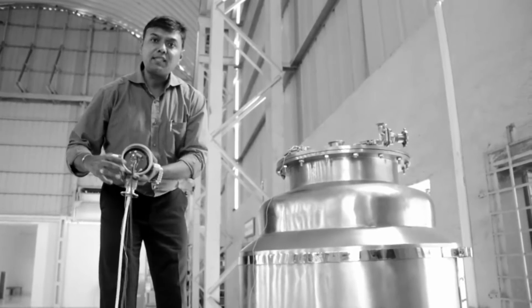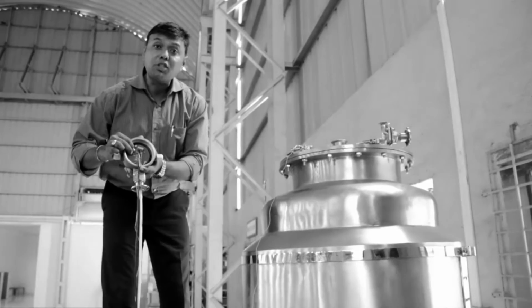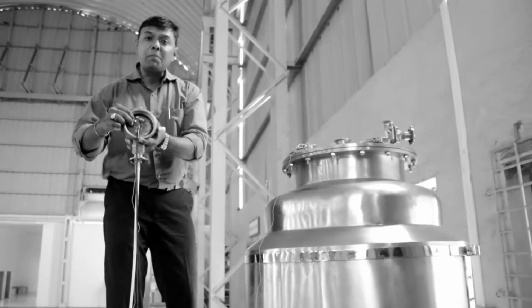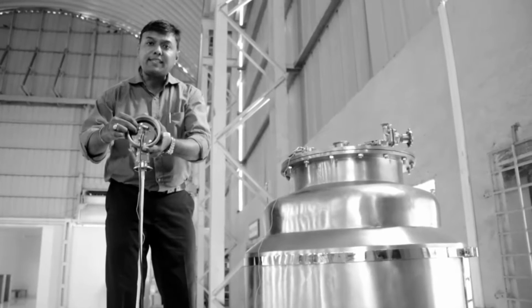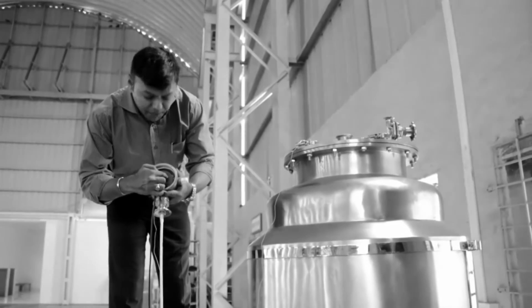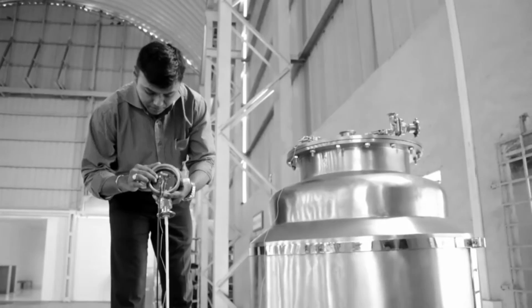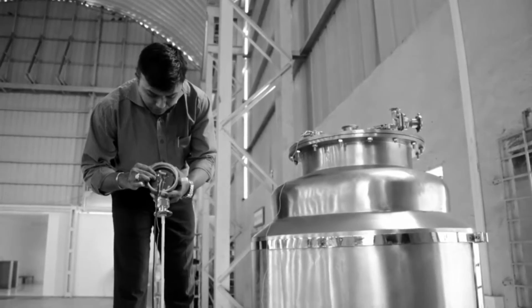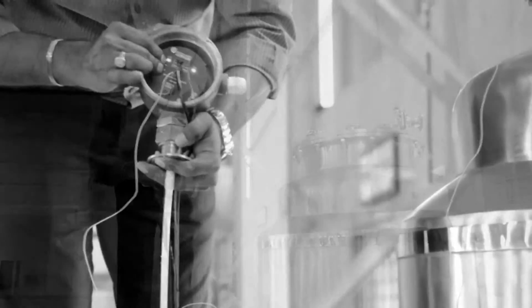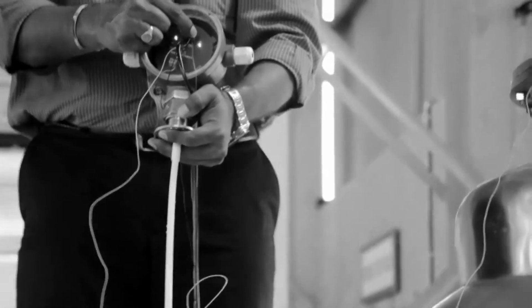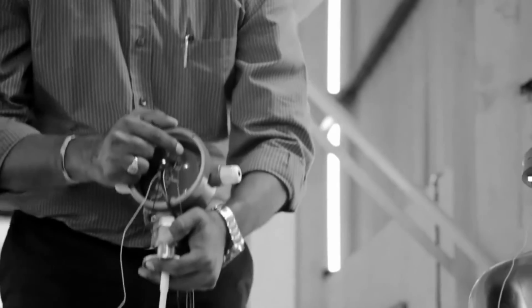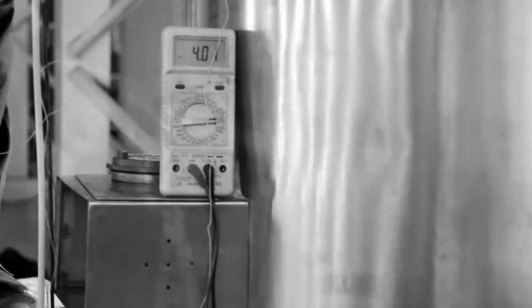We are going to press the minimum and maximum buttons together. When we press the minimum and maximum buttons together for 3 seconds, you will see that the calibration LED starts blinking. You can see that the calibration LED has started blinking. And you can see the 4 milliamps current here.